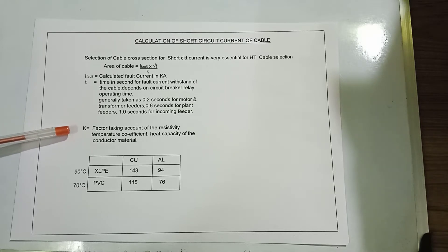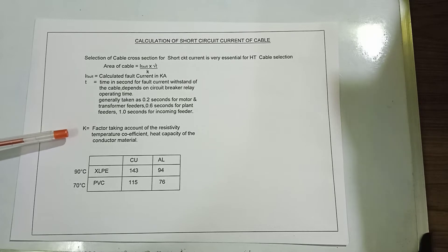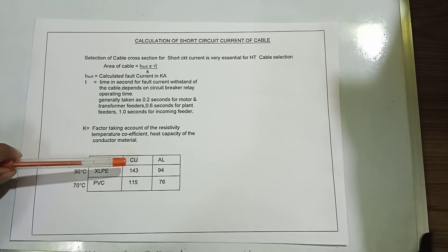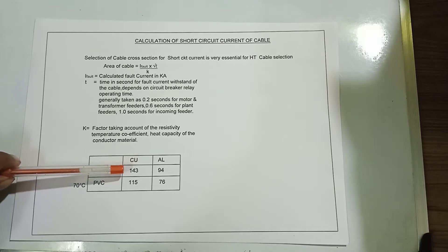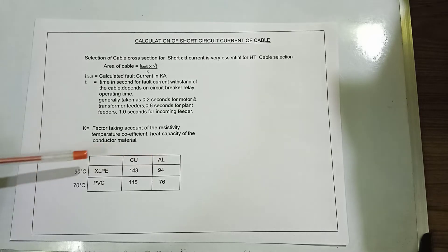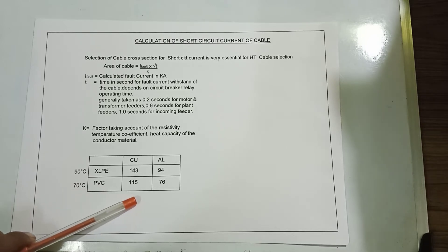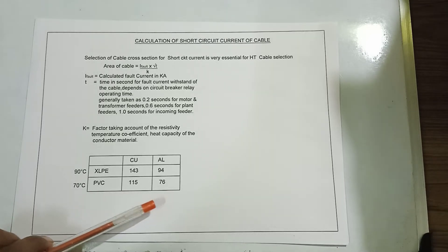k is a factor taking account of the resistivity and temperature coefficient and heat capacity of the conductor material. For XLPE at 90°C: copper k = 143, aluminium k = 94. For PVC cable at 70°C: copper k = 115, aluminium k = 76.